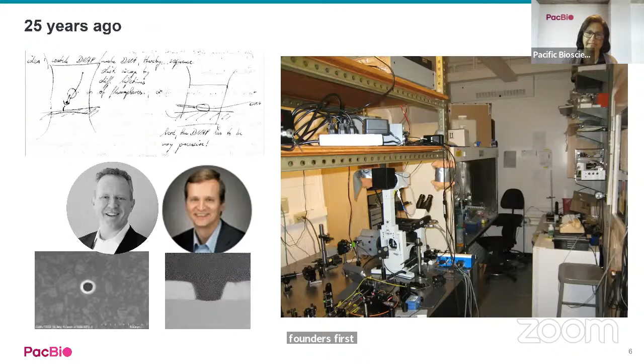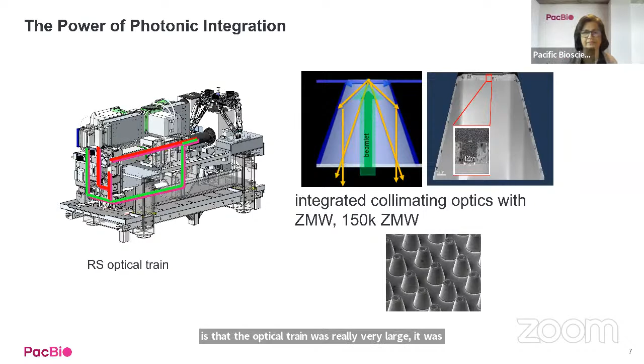As I show you, the first instrument, which was the RS, already had implementation of photonic integration. It was a fused silica substrate that integrated collimated optics with ZMWs. And it allowed anywhere from 75 to 150,000 molecules to be detected. But the problem here, as I highlight with the color lasers, is that the optical train was very large. It was meters long, so it had to be coiled around the system. So what you can see then is that photonic integration is really needed to not just reduce cost, but also to scale. Right, so our interest is in scaling and increasing the read length.